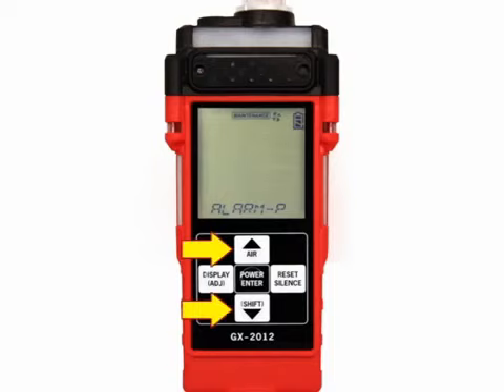Use the air or shift buttons to display the Alarm Points menu item. Press and release the power enter button. You may then select a channel. Use the air or shift buttons to select a channel. The combustible gas channel is shown for example. Press the power enter button to display the warning setting for the combustible channel. It will be flashing. Use the air or shift buttons to change the warning setting. Press power enter to save the setting.